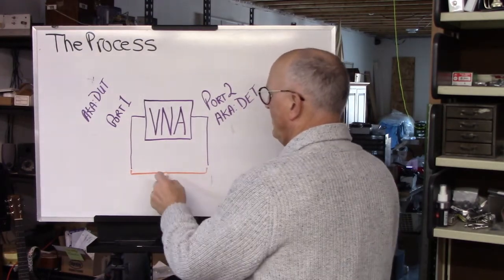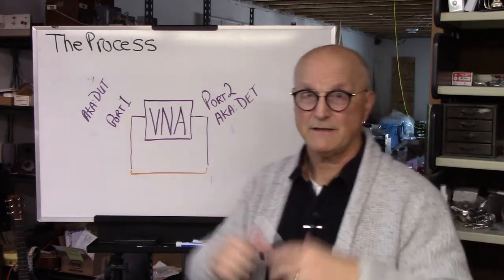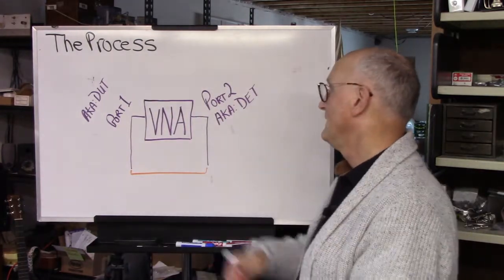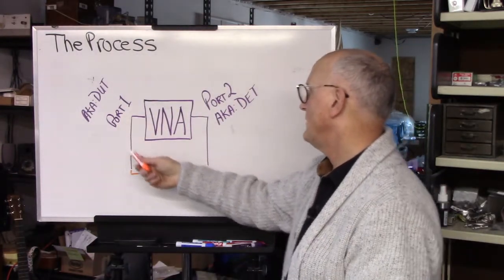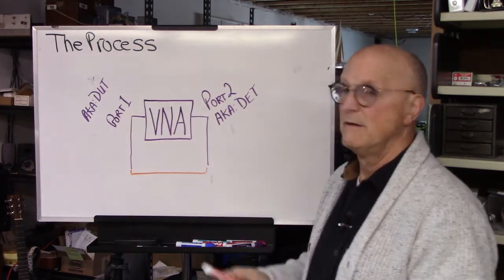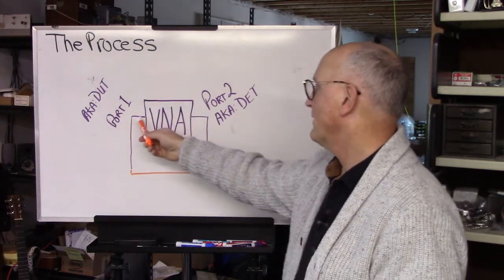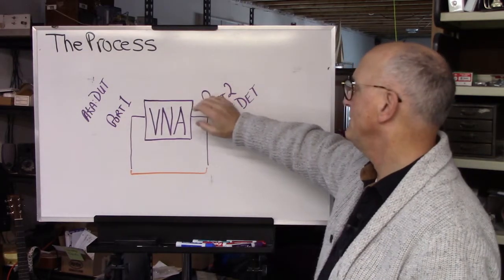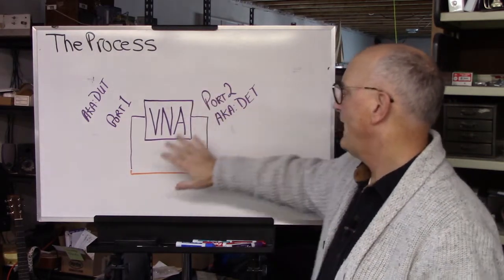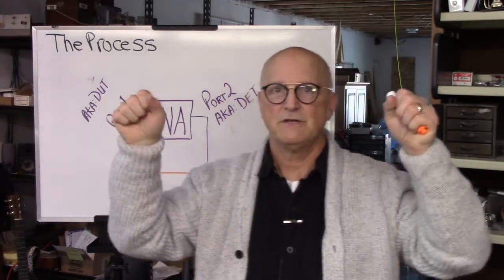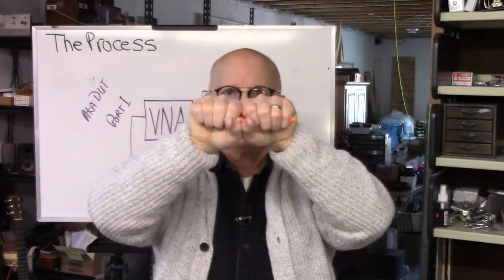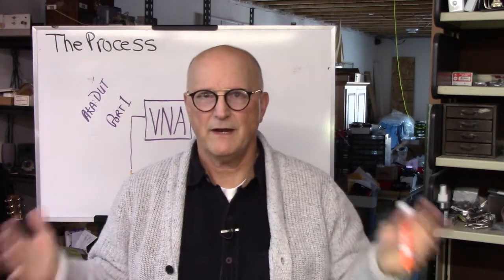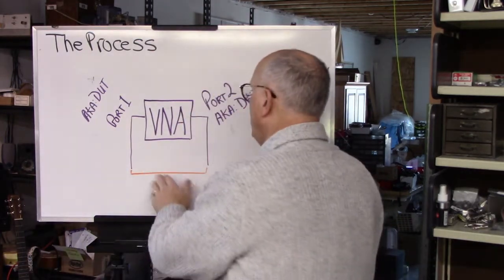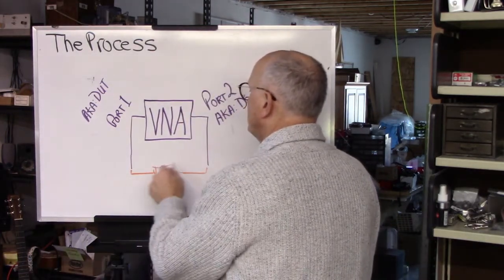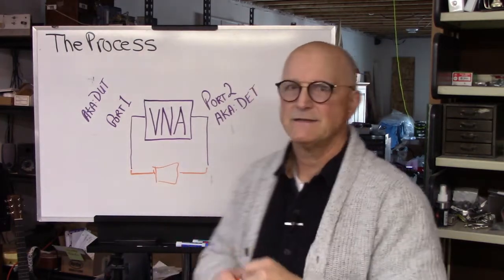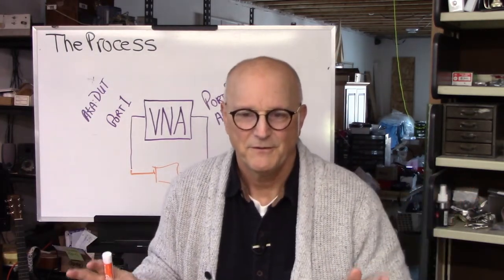So there's the open. And then the second step they have you do is put your through, which is just your adapter to connect the 2 ends of the cables together. Now it's measuring through this whole loop here, the signal levels that are getting from here. It's measuring the amplitude, it's measuring the phase, and so now it knows that if there's no device under test connected and I'm just connected end to end, this is what I can expect. That way, when you put your device under test in here, it says, something is different.